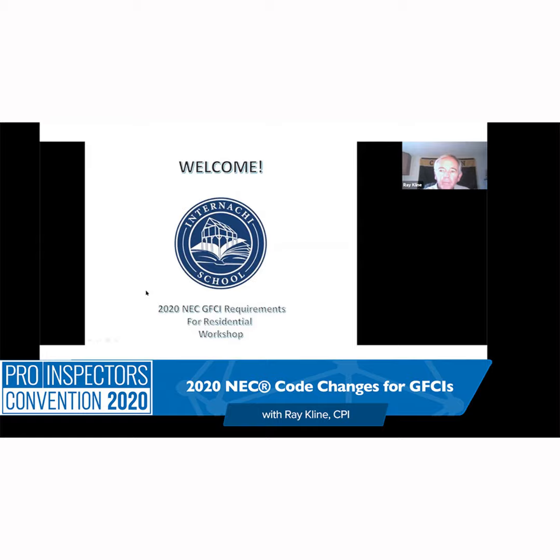Thank you, Ray. Michelle over here says, sometimes when testing GFCI, it will not reset until an upstream GFCI resets. Can you discuss this dynamic? They're wired in parallel, and that should not be. Let me explain that.